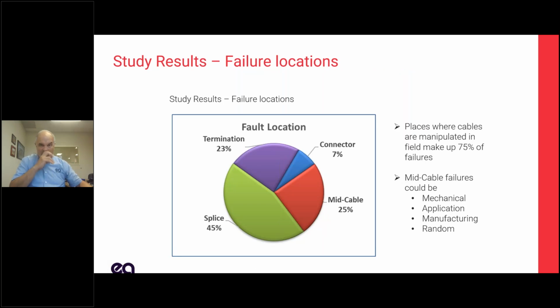But then we get into the interesting stuff. Where did they fail? And you can see here that we've got splices, terminations, connectors, and mid-cable. Okay, everything but the mid-cable is where a human touched that cable, played with that cable, modified that cable, worked with the stress control of that cable in the field. And so you can see that 75% of the failures are at the point where somebody worked with the cable out in the field. So that's our first clue that something's going on, and it's usually related to a person working with the cable. Now, mid-cable failures, a lot of it was mechanical. It could be manufacturing related. Sometimes they were defective cables, but it's hard to say what those are from.